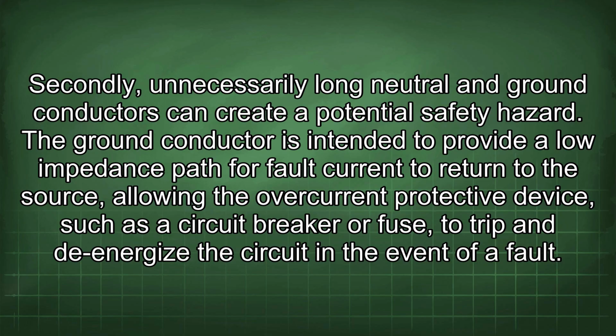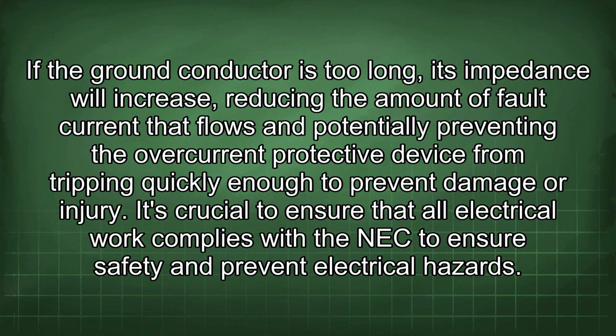Secondly, unnecessarily long neutral and ground conductors can create a potential safety hazard. The ground conductor is intended to provide a low impedance path for fault current to return to the source, allowing the overcurrent protective device, such as a circuit breaker or fuse, to trip and de-energize the circuit in the event of a fault. If the ground conductor is too long, its impedance will increase, reducing the amount of fault current that flows and potentially preventing the overcurrent protective device from tripping quickly enough to prevent damage or injury. It's crucial to ensure that all electrical work complies with the NEC to ensure safety and prevent electrical hazards.